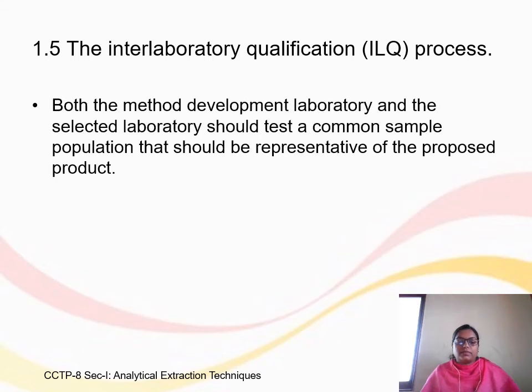The interlaboratory qualification, ILQ, process. Both the method development laboratory and the selected or designated laboratory should test a common sample population that should be representative of the proposed product. This means the designated laboratory should apply the validated method developed in that laboratory to the proposed product, the same as the development laboratory.